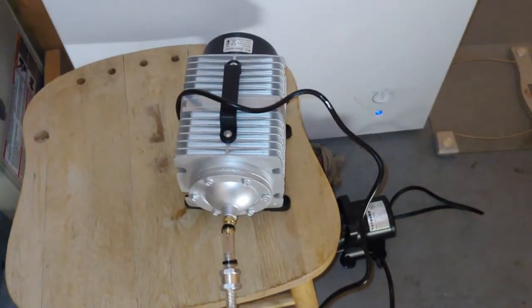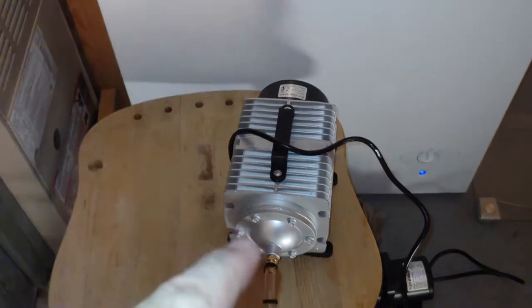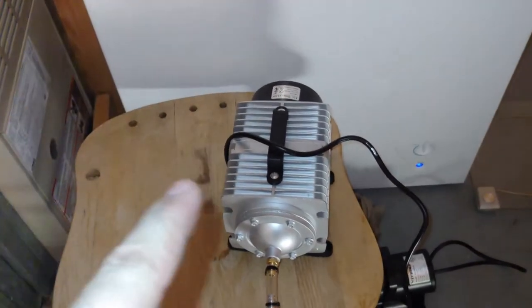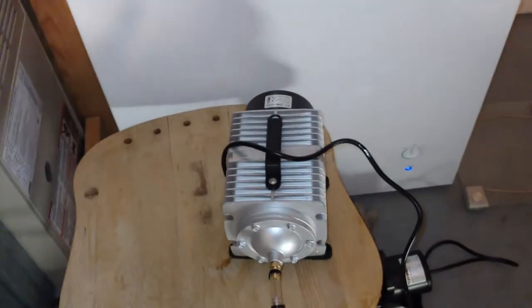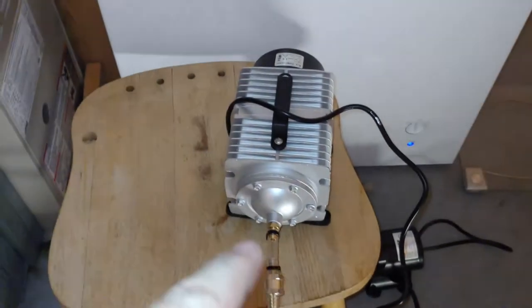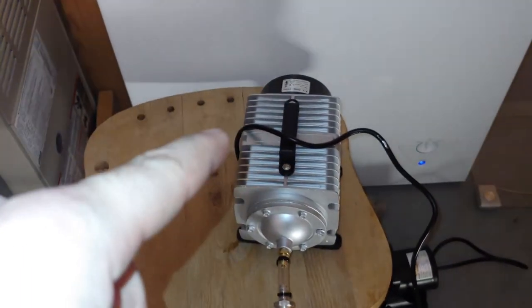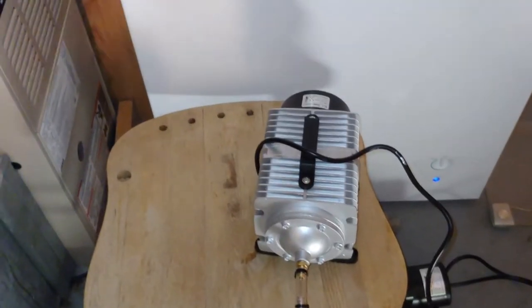It's all nice and dandy to say 'oh I've got a pump that can do 110 liters per minute,' but you're choking it off to 50 liters per minute. Now what's happening is when you're choking it off, you're heating it up. That back pressure causes a lot of heat in these pumps.